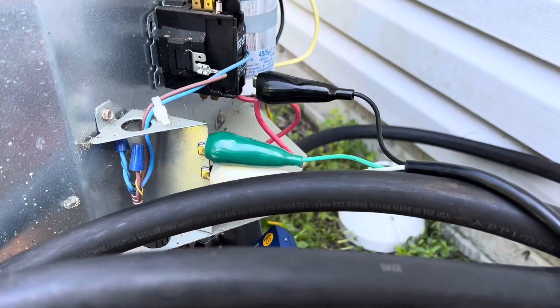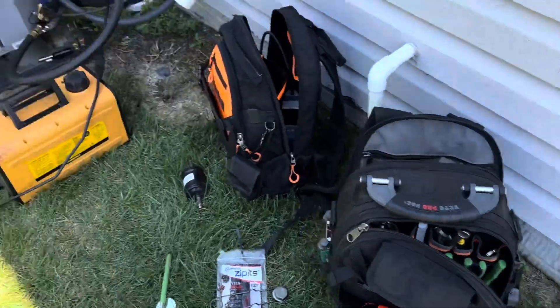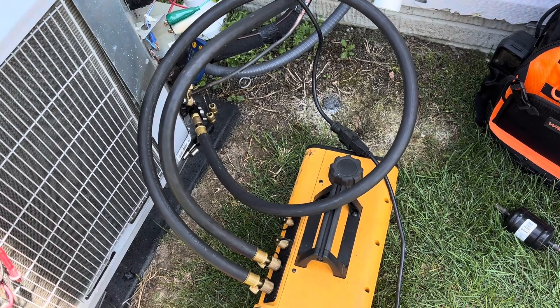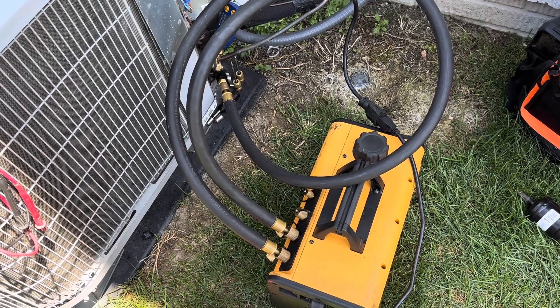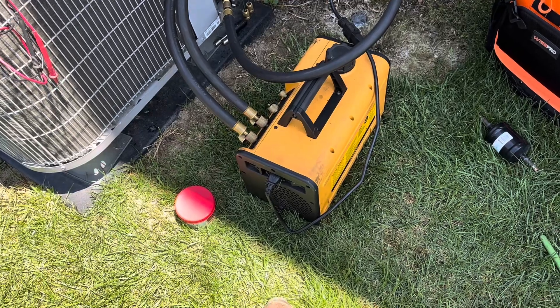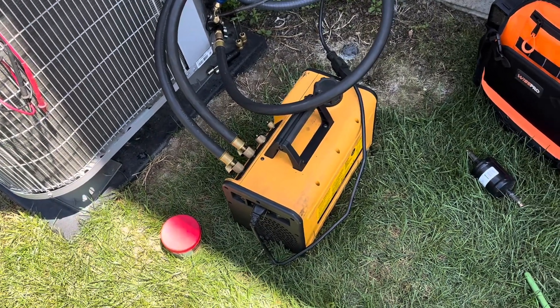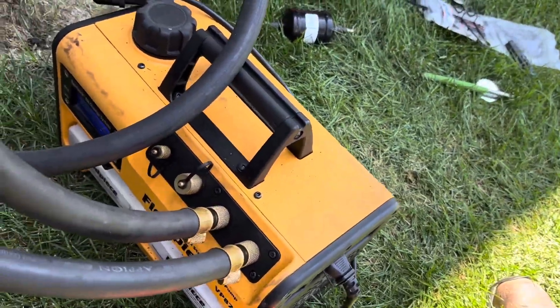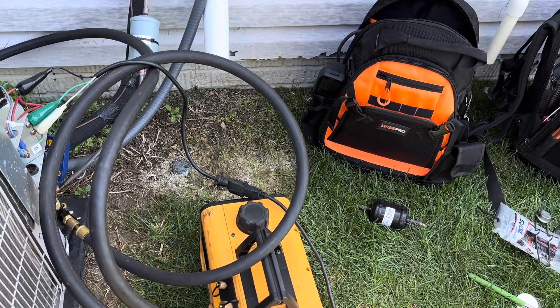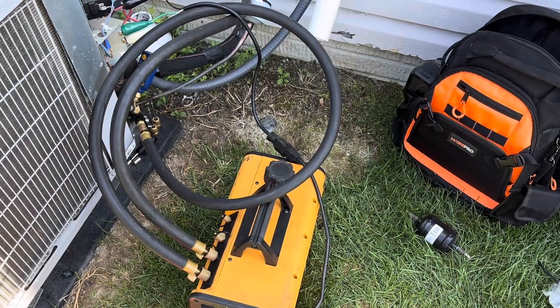I've got my cheater cord here for electric. There was an outlet right here but it's hooked up to a GFCI, and my pump does not like GFCI outlets — every time I try to use one it trips the GFCI. It did it even when the pump was new. Sometimes it'll go 10 or 15 minutes and trip it, sometimes it trips right away like today. Anybody else with the Fieldpiece vacuum pump — this is the VP87 — let me know if you guys have issues with them tripping GFCIs. They don't trip the breaker, just the GFCI.